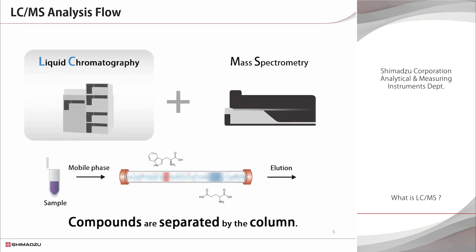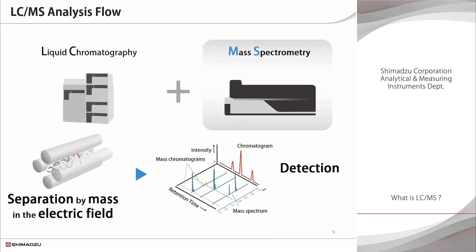On the other hand, LC-MS uses volatile solvents such as formic acid and acetic acid, rather than phosphoric acid buffers and other non-volatile solvents often used as mobile phases in LC. The following is a simple overview of the LC-MS analysis flow. First, the sample is injected into the LC unit. The compounds in the sample are separated by differences in their affinity for the fixed and mobile phases in the column attached to the LC unit. The compounds separated by the column are then ionized in the mass spectrometer. The compounds are separated by the difference in their masses and then reach the detector. As a result, with LC-MS, compounds are separated in two stages by LC and MS, so separation selectivity is dramatically higher than with LC, making LC-MS suitable for the analysis of complex samples.